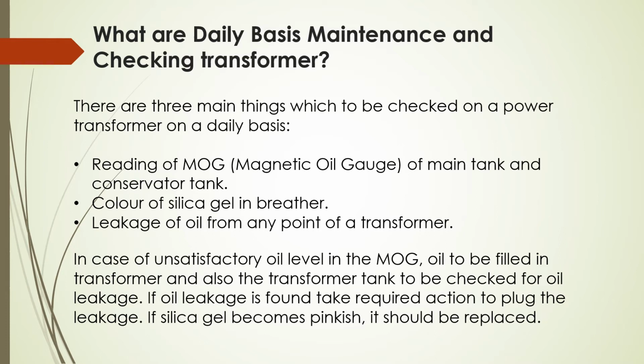What are daily basis maintenance and checking of transformer? There are three main things which are to be checked on a power transformer on daily basis: reading of MOG, magnetic oil gauge, of main tank and conservator tank, basically to indicate oil level in the transformer; color of silica gel in breather; leakage of oil from any point of transformer.